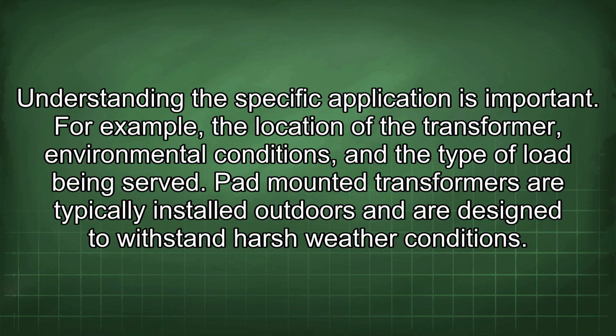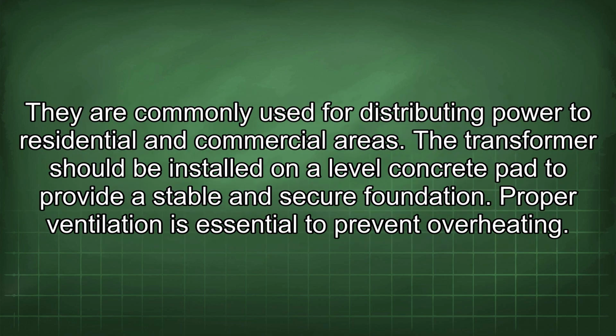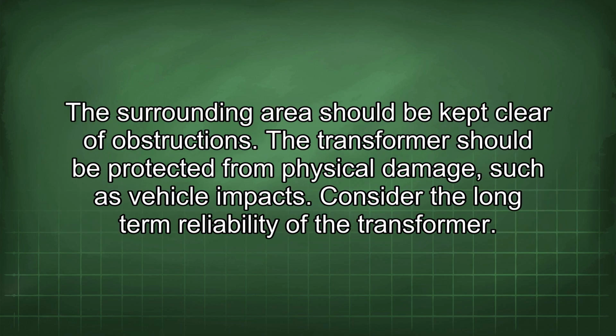Understanding the specific application is important. For example, the location of the transformer, environmental conditions, and the type of load being served. Pad-mounted transformers are typically installed outdoors and are designed to withstand harsh weather conditions. They are commonly used for distributing power to residential and commercial areas. The transformer should be installed on a level concrete pad to provide a stable and secure foundation. Proper ventilation is essential to prevent overheating. The surrounding areas should be kept clear of obstructions. The transformer should be protected from physical damage, such as vehicle impact.